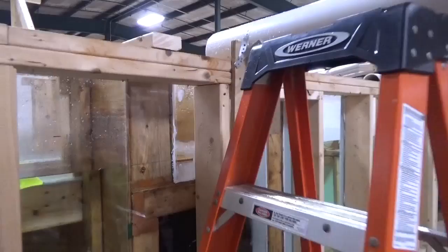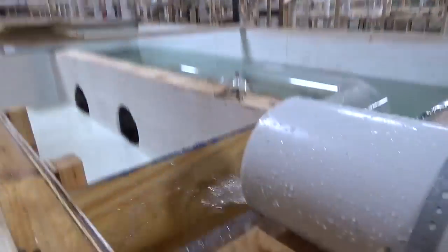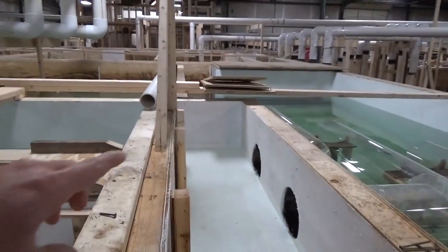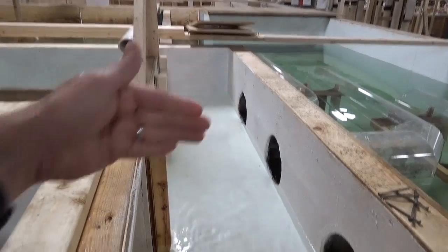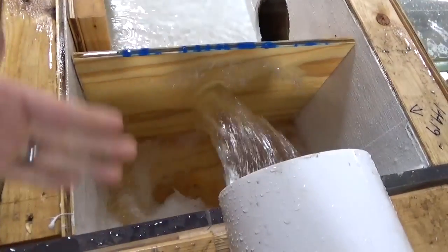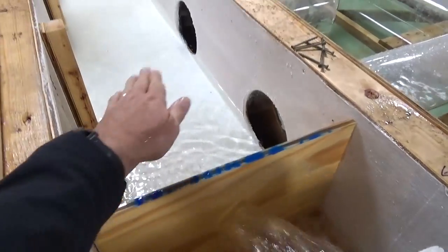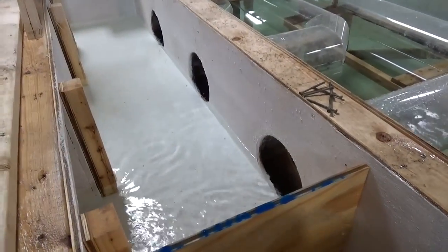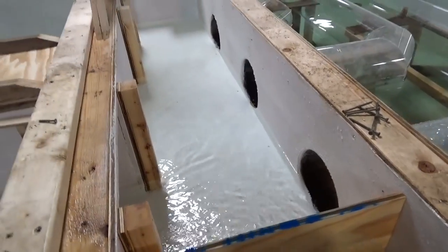This baffle seems to contain that very well. We're going to talk about, during witness testing, bringing that wall back in a little bit and eliminating that dead zone on that side. Actually, it would be this side. We've mirror imaged the pipe so we could see its impact on the wet well we modeled in detail.